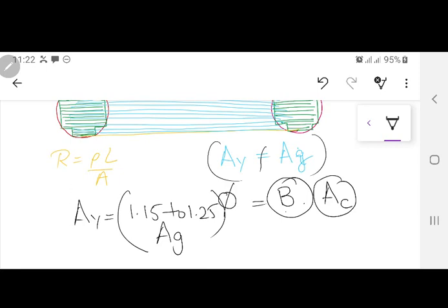Why? Because in the yokes you have a larger yoke area, so the B value of the yoke is decreased. Same flux is passing. When the area of the yoke is increased, what will happen? B will reduce. So less B means less core losses inside the yoke. So you can increase it from 15 to 25% of the total gross area that you have.